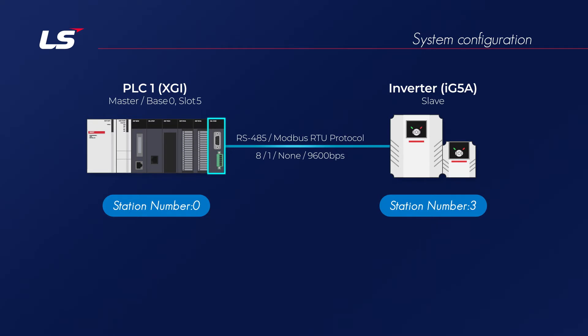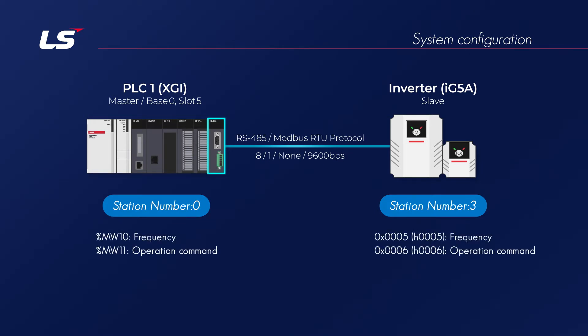You can write and read data to and from the drive via communication. Here we will control the drive by changing reference frequency and operation command. If you write MW10 of XGI to 0x0005 of drive, the reference frequency of drive is updated by MW10 data. And if you send MW11 of XGI to 0x0006 of drive, MW11 data will be used as the run command.